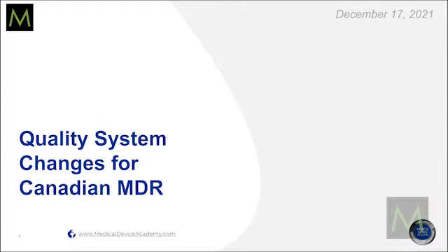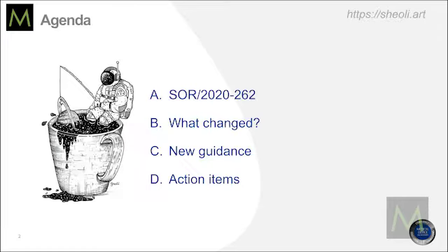The work should have been something you already were working on long ago. Very short agenda here. Number one, what is the new regulation? It actually has a regulation number. The original MDR is SOR 98-282. This new one that was released — I think the law behind it is called Vanessa's Law — it's SOR 2020-262. The draft was back in 2019, so people have known about this for a really long time if they were following Canada.